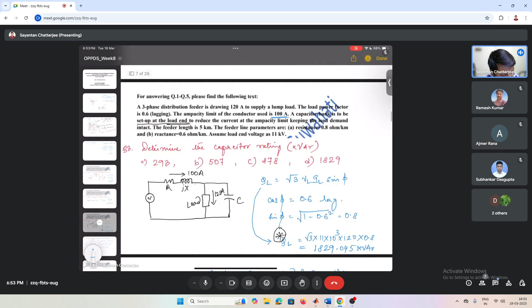1829, so this much extra value needs to be taken up by the extra capacitor connected. So Q capacitor would be Q line minus Q, this Q value. So Q line was 1829.05045, let us not take that part, and 1321.8. So just 1829 minus 1321 is 507, approximately. This is the amount of reactive power that needs to be delivered by the capacitor.